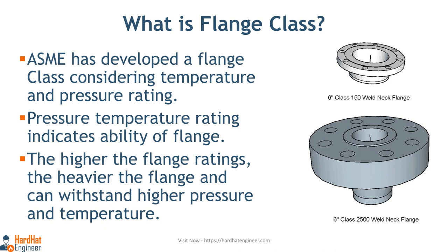ASME has developed a flange class that considers temperature and pressure ratings. What is this pressure-temperature rating? Piping materials such as carbon steel, stainless steel, and alloy steel have different mechanical and chemical properties. The same material can handle different amounts of stress at different temperatures. Based on the material's ability to handle stresses at a given temperature, ASME B31-3 has determined the maximum allowable stress value of the material at a specific temperature.